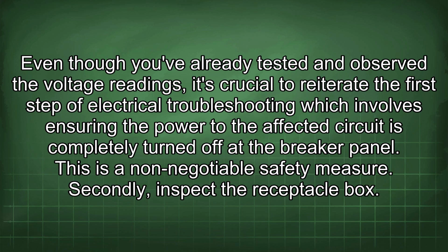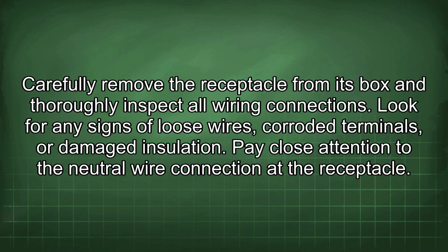Even though you've already tested and observed the voltage readings, it's crucial to reiterate the first step of electrical troubleshooting, which involves ensuring the power to the affected circuit is completely turned off at the breaker panel. This is a non-negotiable safety measure. Secondly, inspect the receptacle box. Carefully remove the receptacle from its box and thoroughly inspect all wiring connections. Look for any signs of loose wires, corroded terminals, or damaged insulation.